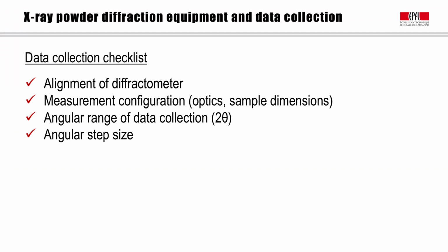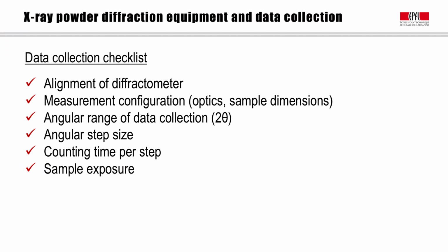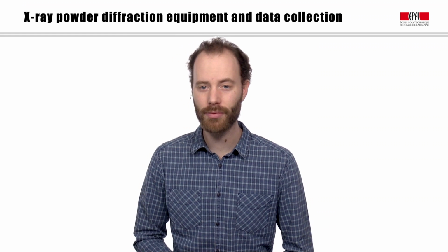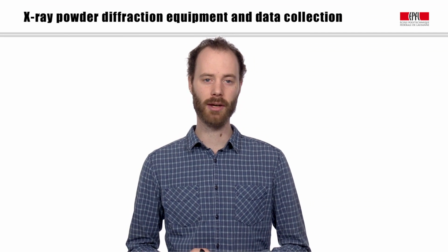For most in-house diffractometers, a step size of about 0.02 degrees 2 theta is used, and the counting time per step is usually a compromise between the optimal signal-to-noise ratio and practical considerations such as the available time for measurements or acceptable sample exposure. The development of high-performance X-ray detector systems in the last decades has allowed us to drastically reduce measurement times and thus to minimize exposure times of hydrated samples to a couple of minutes.